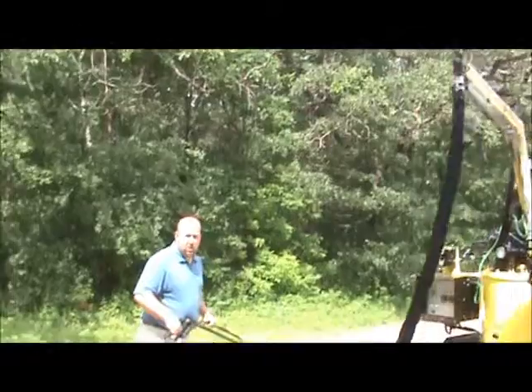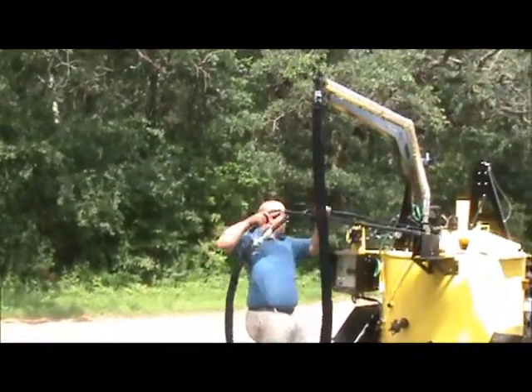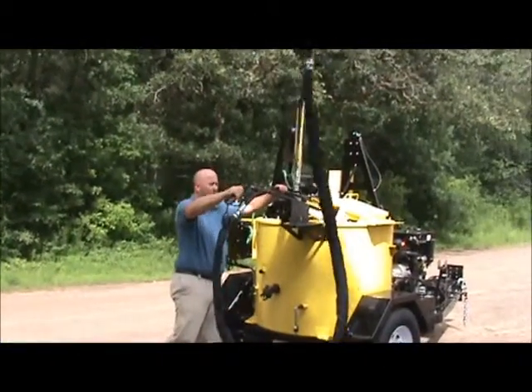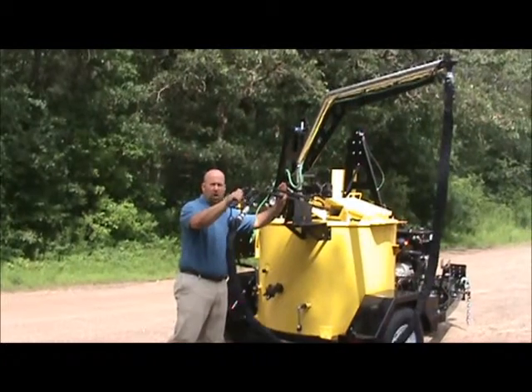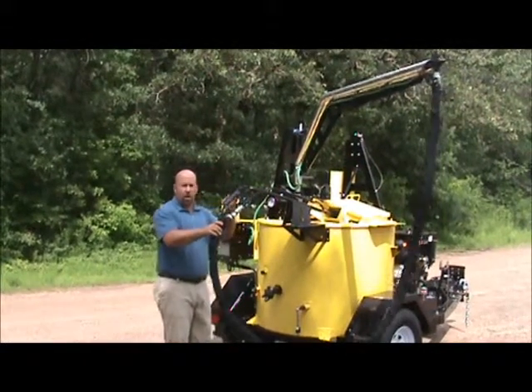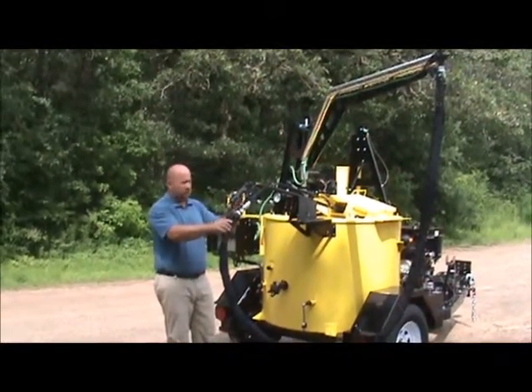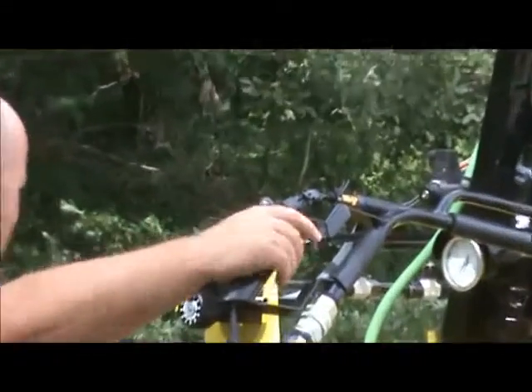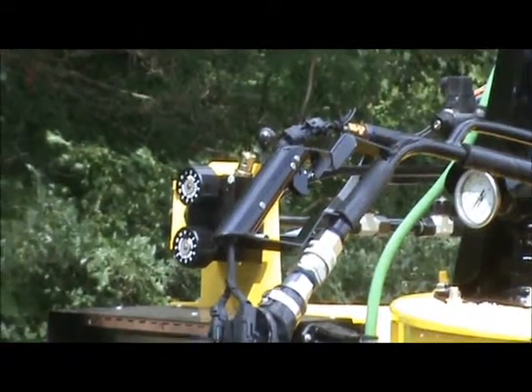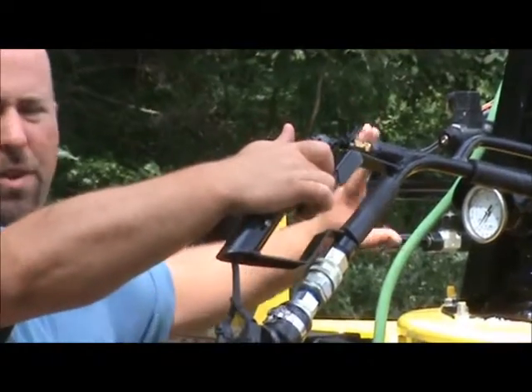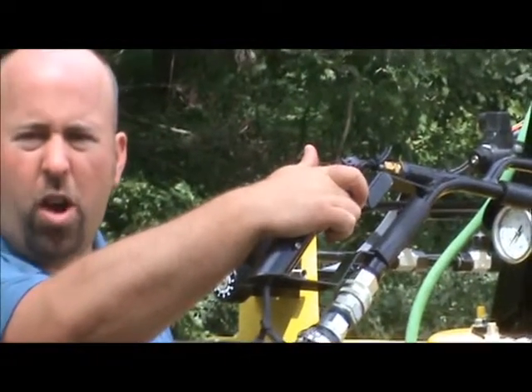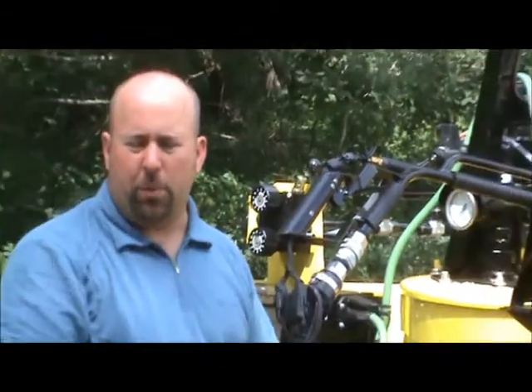Now this allows us to stick our wand right back inside the kettle to establish flow. Now the switch I was talking about is located right here on the wand. You can hear me click the switch. When the wand control switch is in the wand control position, the pump will be stopped until we pull the switch. Then the pump is going to start. When we let go of the switch, the pump is going to stop.